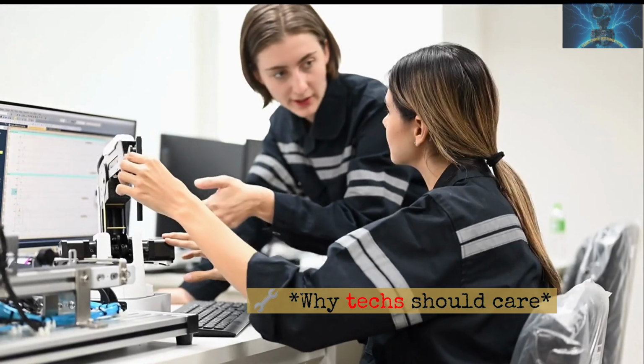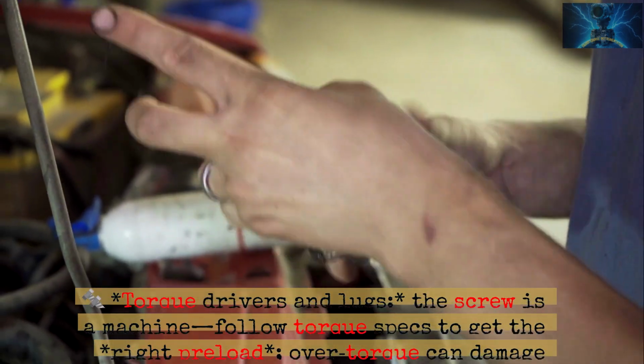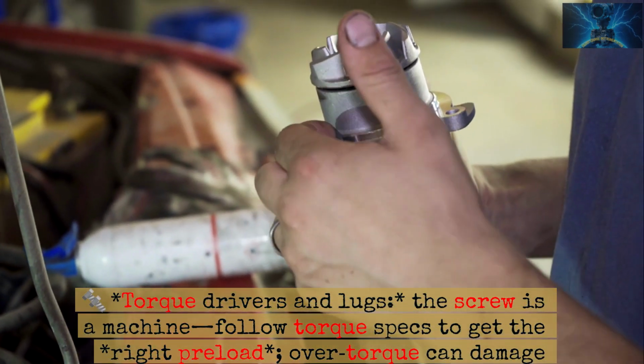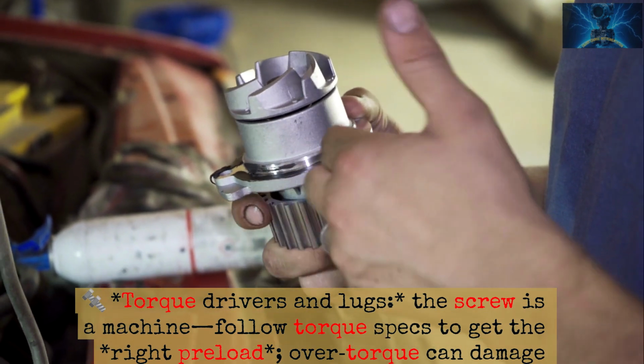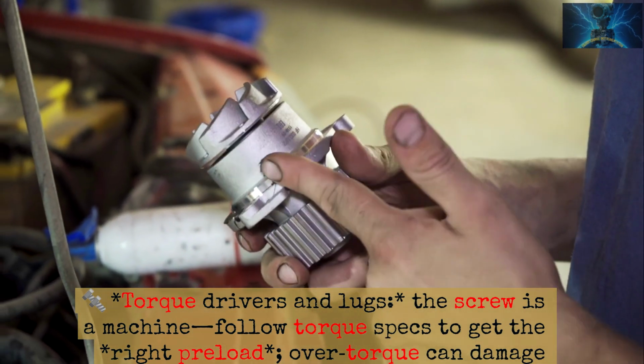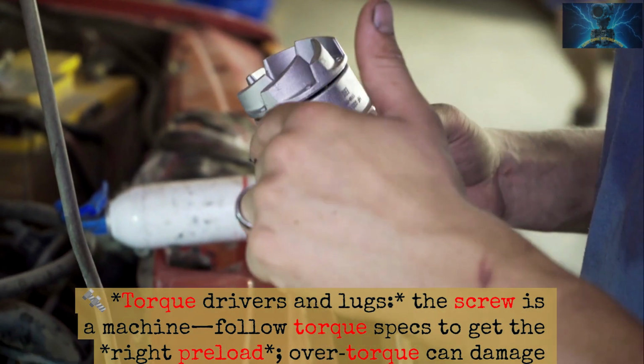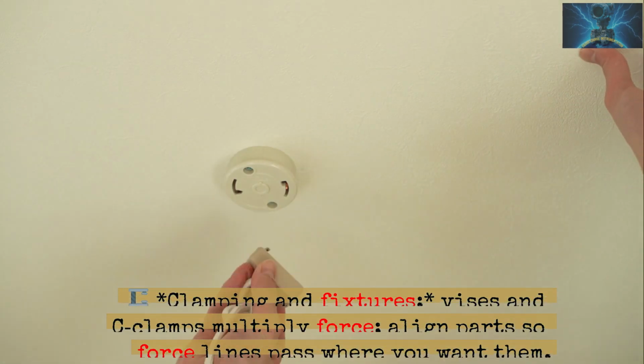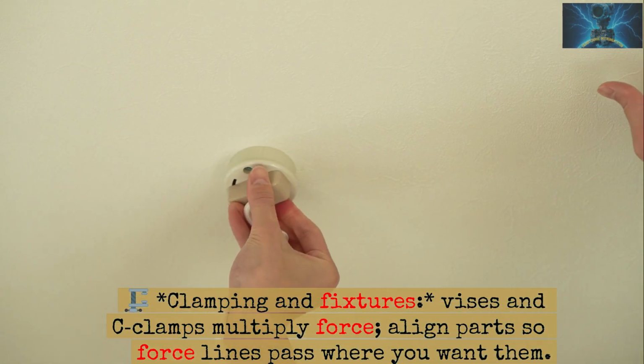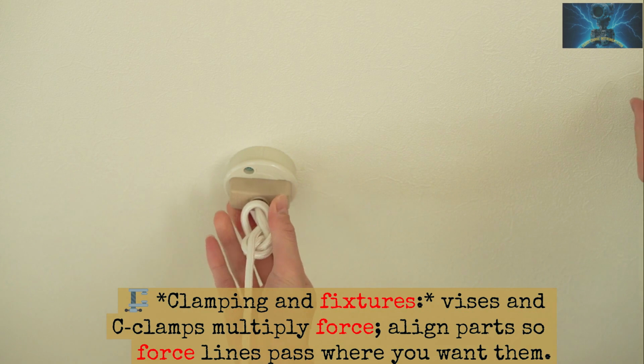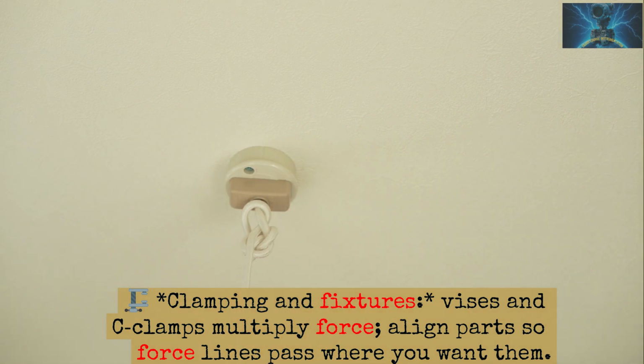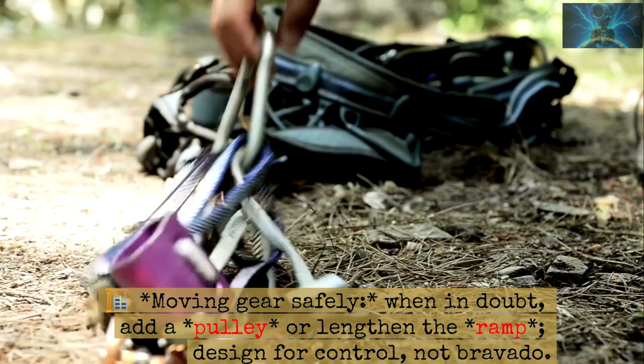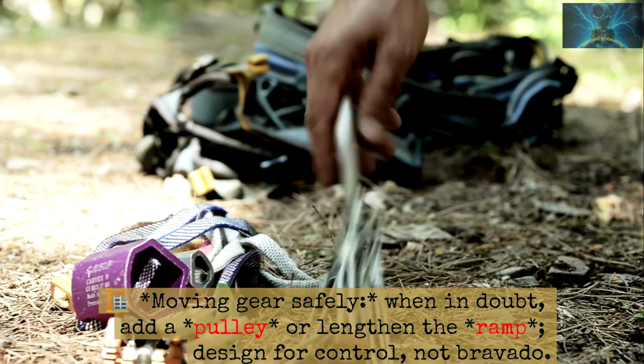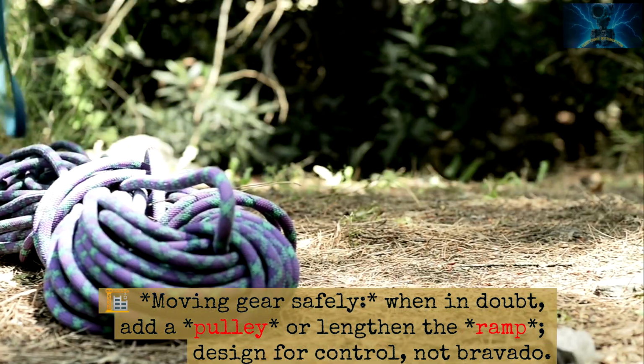Why should techs care? Torque drivers and lugs: the screw is a machine. Follow torque specs to get the right preload. Over-torque can damage copper and create hotspots. Clamping and fixtures: vices and C-clamps multiply force. Align parts so force lines pass where you want them. Moving gear safely: when in doubt, add a pulley or lengthen the ramp. Design for control, not bravado.